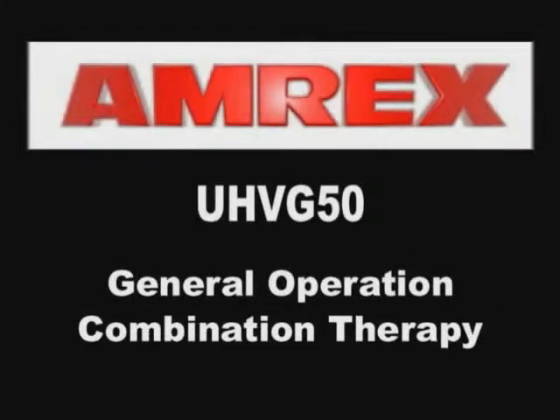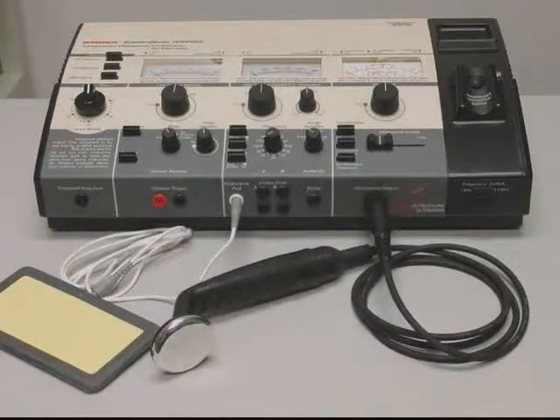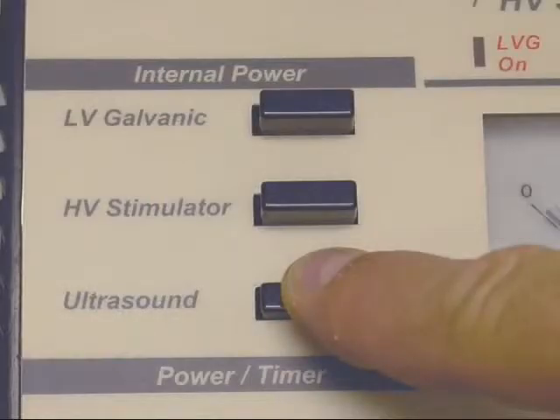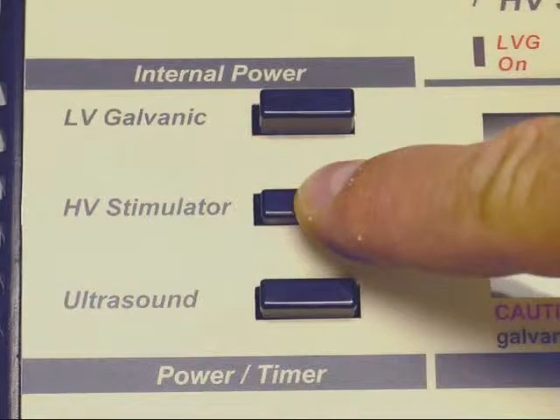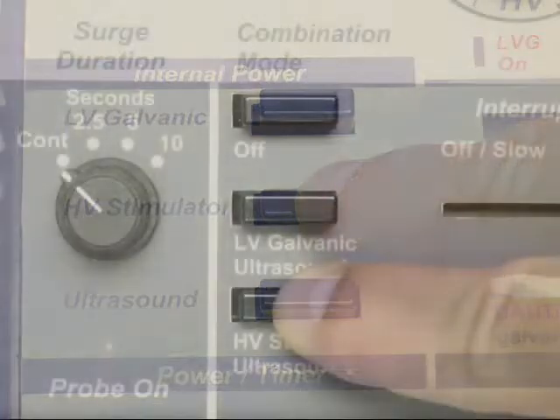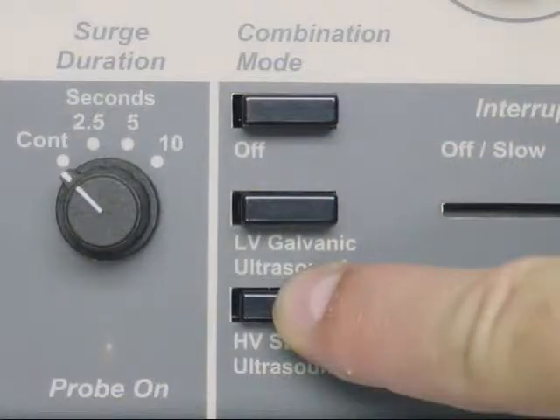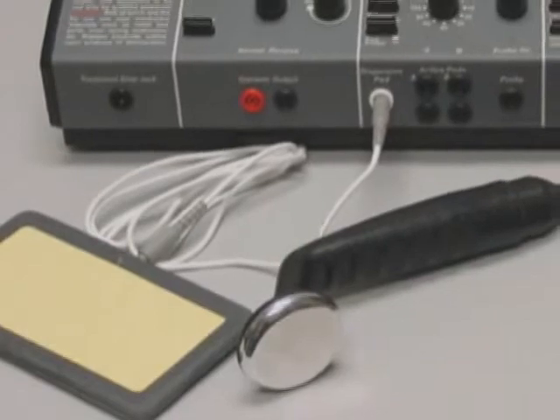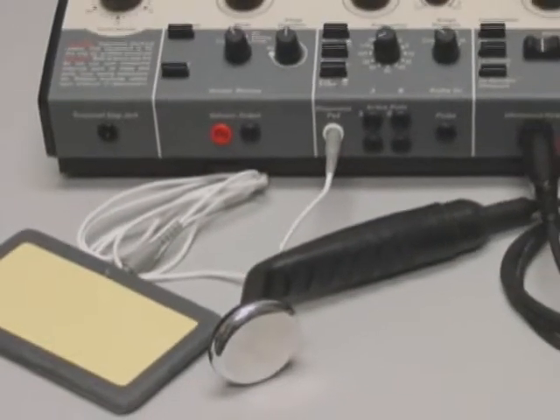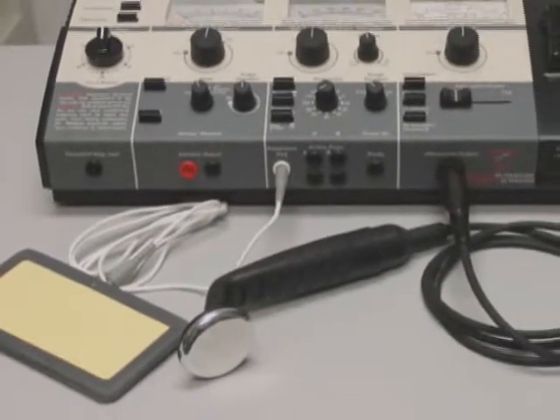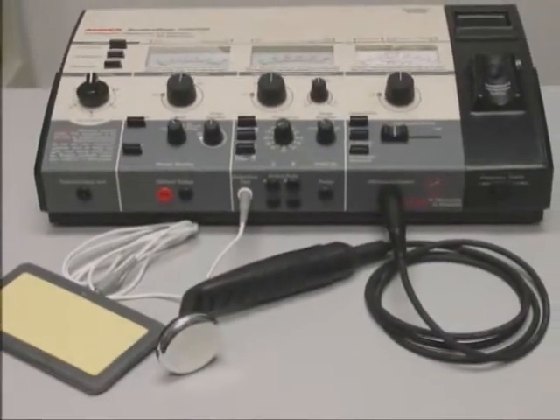UHVG50 General Operation, Combination Therapy. Depress the UHVG50 internal power ultrasound switch, the internal power high voltage stimulator switch, and the combination mode high voltage stimulator ultrasound switch to their on-down positions, and properly connect a dispersive pad to the UHVG50 to enable high voltage pulsed DC stimulation and ultrasound combination therapy.